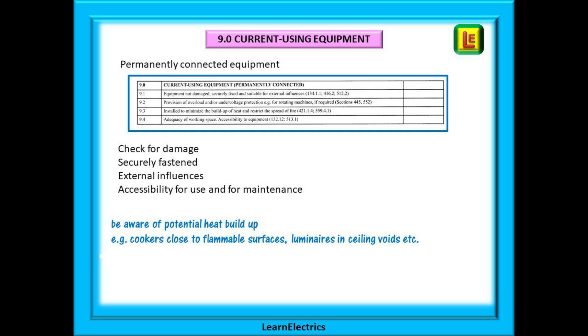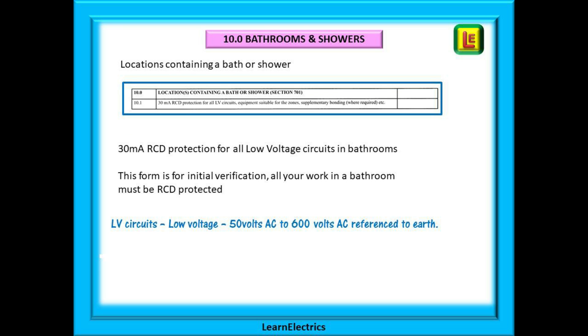Section 9 covers permanently connected equipment — any equipment that is hardwired into the fixed installation, items that are not unpluggable. These carry extra dangers as they cannot be unplugged in an emergency and cannot be moved easily. Think about where they are positioned: are they near flammable surfaces? Lighting that penetrates the ceiling may introduce heat into the ceiling void. Is the equipment securely located so that it remains in place? Is there access for maintenance?